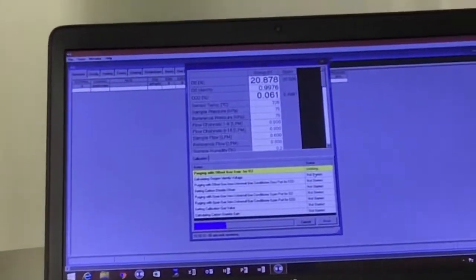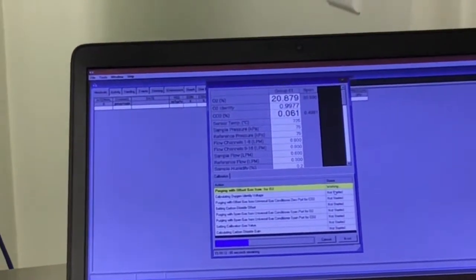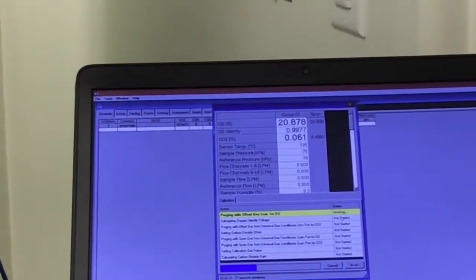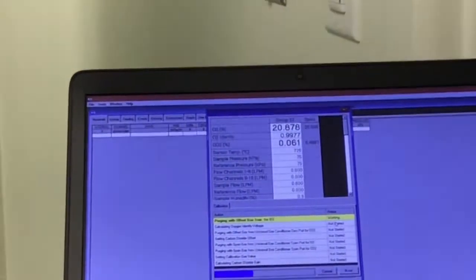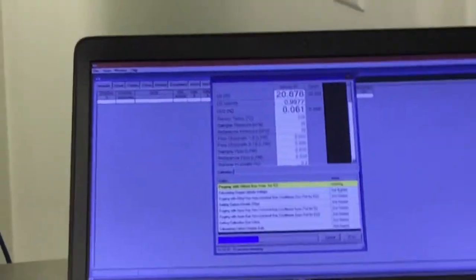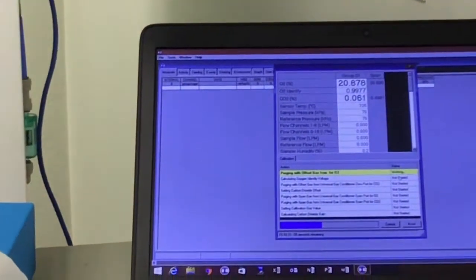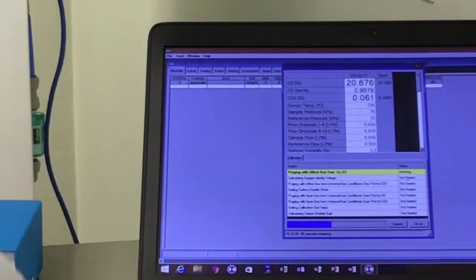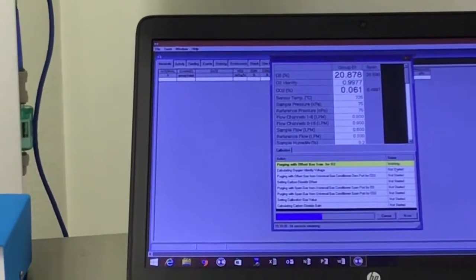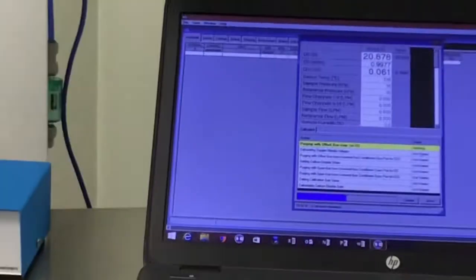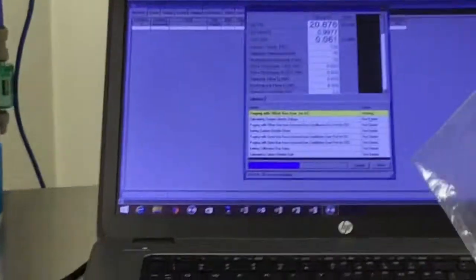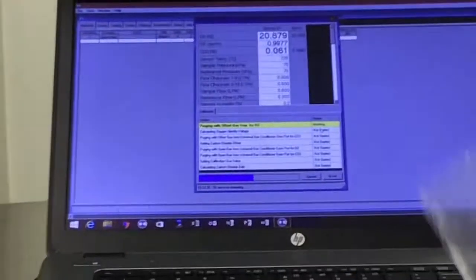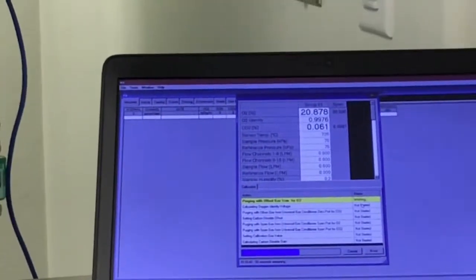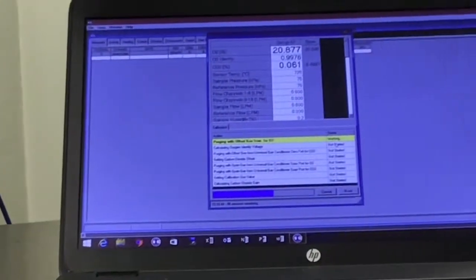So it will do its thing. Two things can happen for it to fail, usually. Usually the gas is not on. Most of the time, that's one of the things. The second one will be that you don't have enough pressure on your gas tank. And usually you have messages such as, your O2 reference air is out of range. That means your gas is not turned on. So it will give you a message.